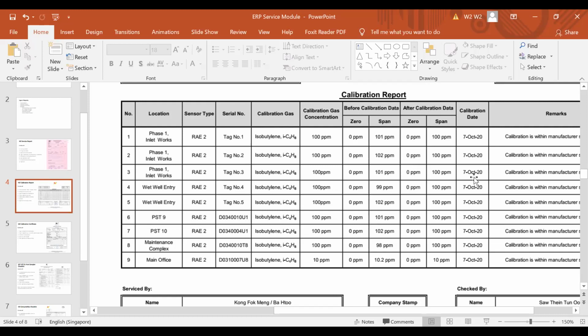I always say the calibration is successfully done if the span after calibration is exactly the same as the calibration gas concentration. Generally, that is our reference aim point. So basically the calibration gas concentration must match the span on the right hand side. Yeah, because this calibration gas is a primary standard, and this equipment is a secondary standard. So basically you're using a primary standard to adjust internally to read 100.